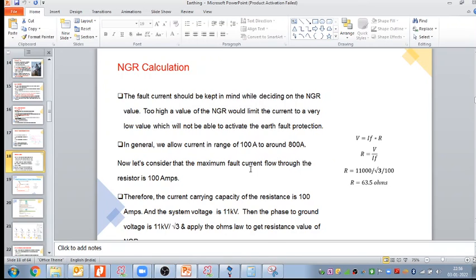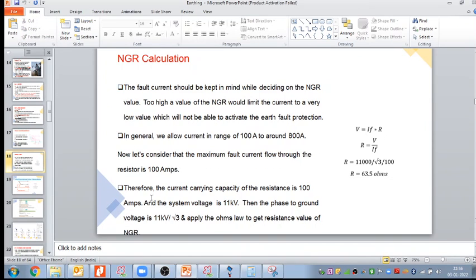Now let's consider the maximum fault current flowing through the NGR is 100 ampere. So if it is 100 ampere, we can derive the NGR rating as 63.5 ohm. The current carrying capacity of the resistance is 100 ampere, and the system voltage is 11 kilovolts. The phase to ground voltage is 11 by root 3, and applying Ohm's law, we can get the resistance value of the NGR. This is how we can find the NGR.